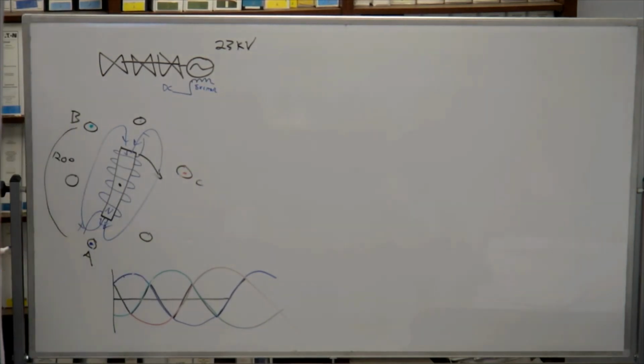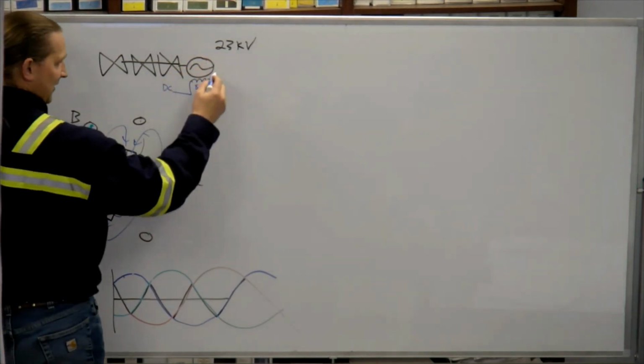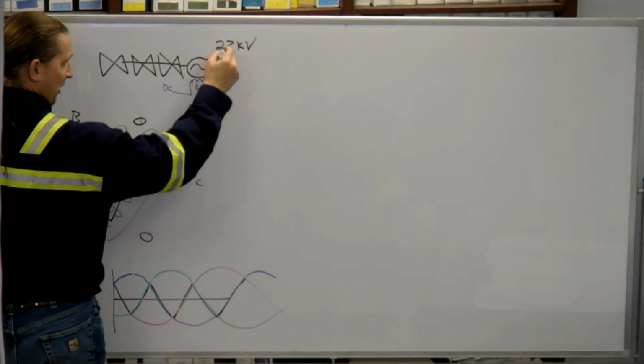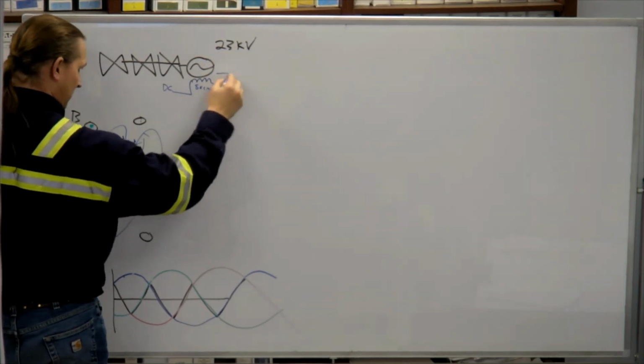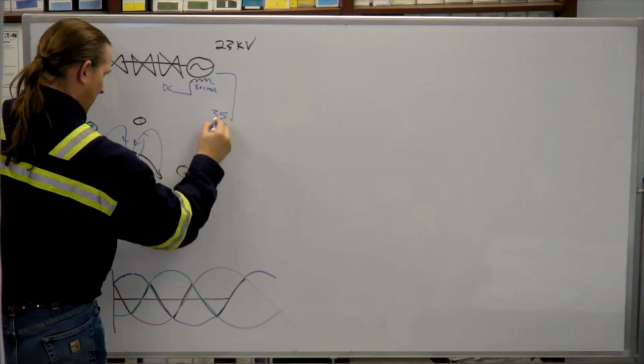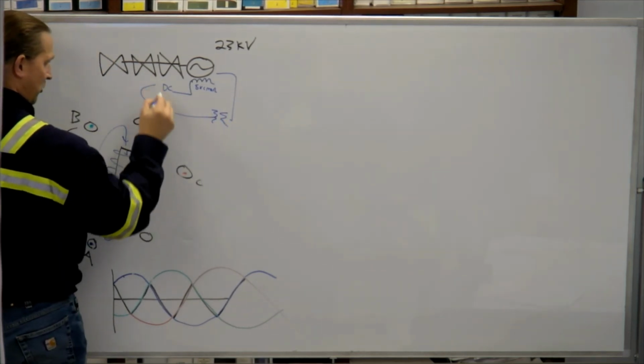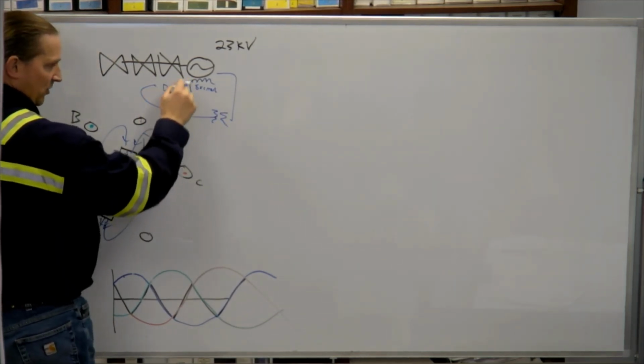That's the box downstairs, right? On the first level? Yes. Hang on. Cabinet? So on the second floor, there's an excitation breaker. And on the first floor, there's an excitation transformer. So the excitation transformer comes off this 23,000. And it's got a transformer, and then it goes to a voltage control cabinet, which puts DC voltage on the exciter.